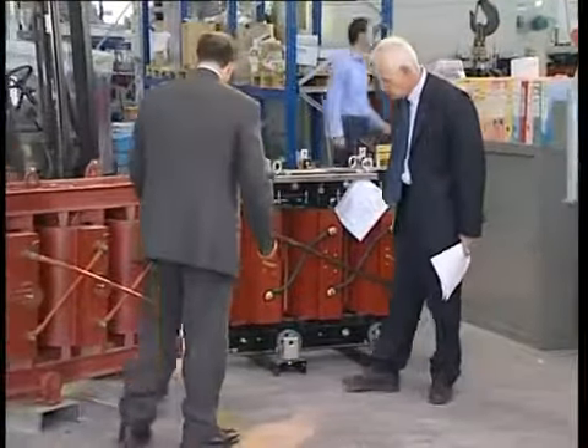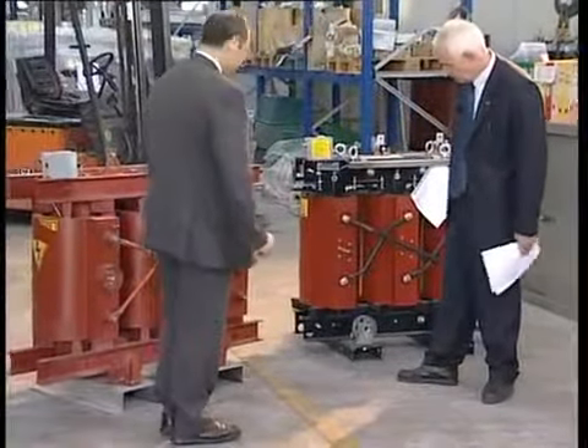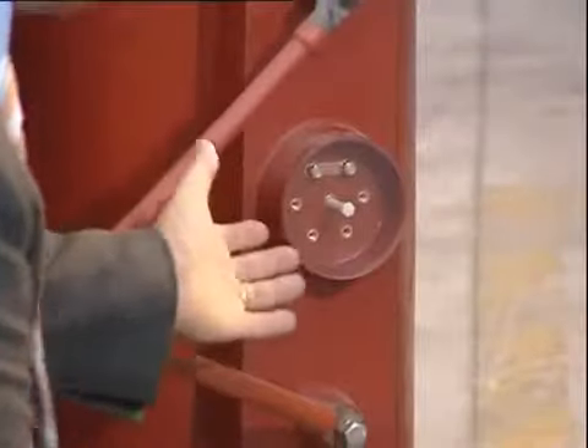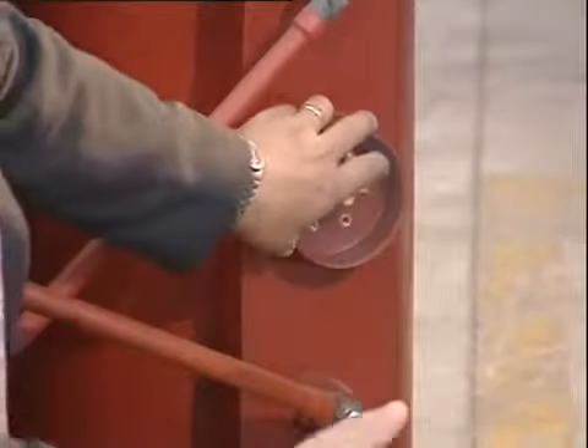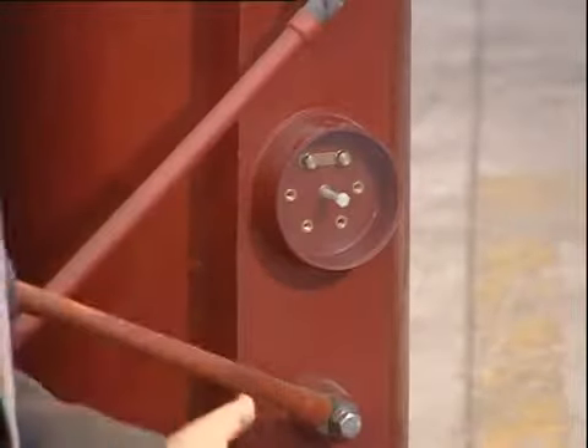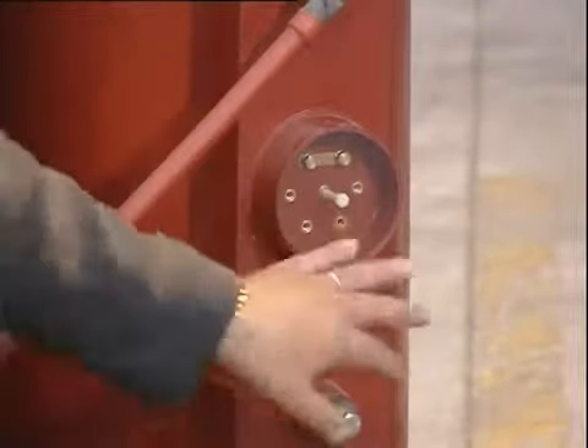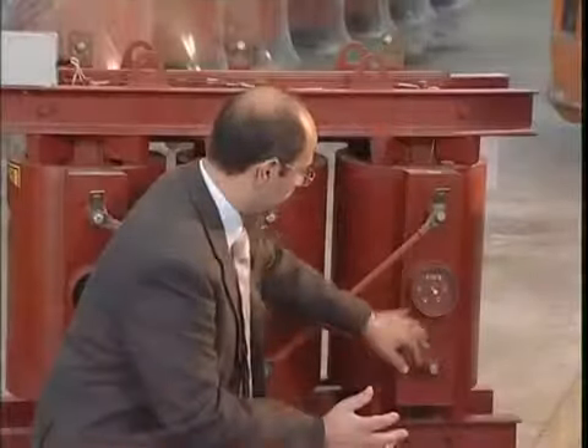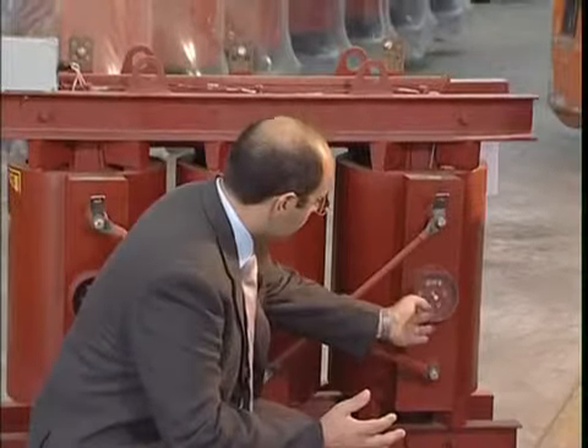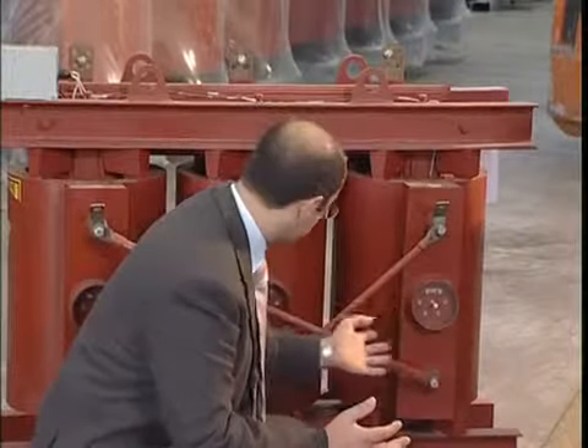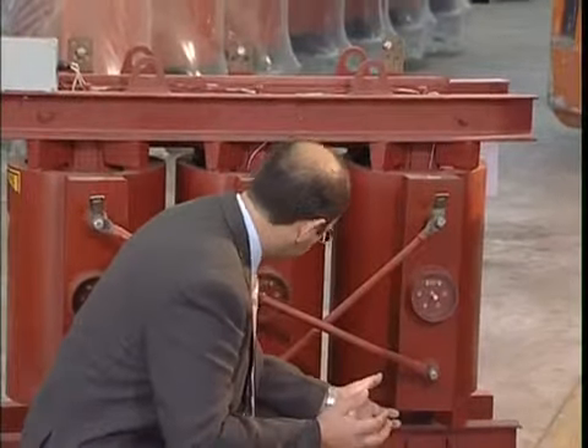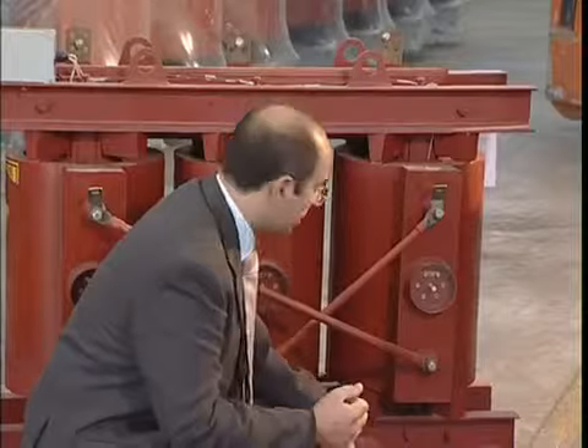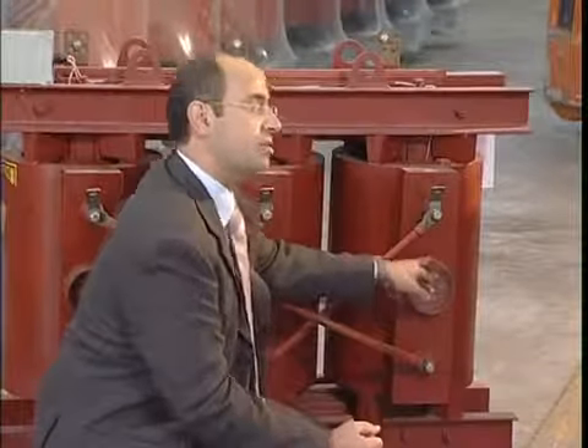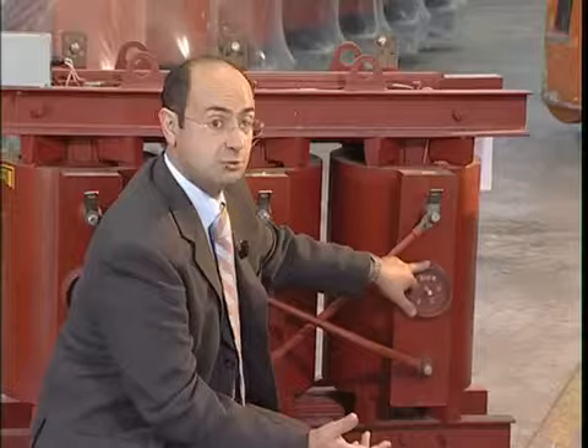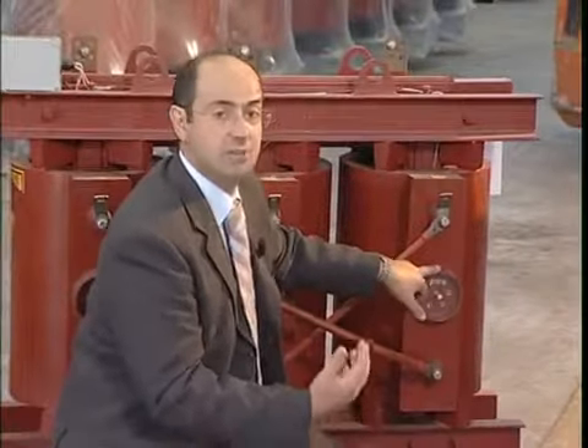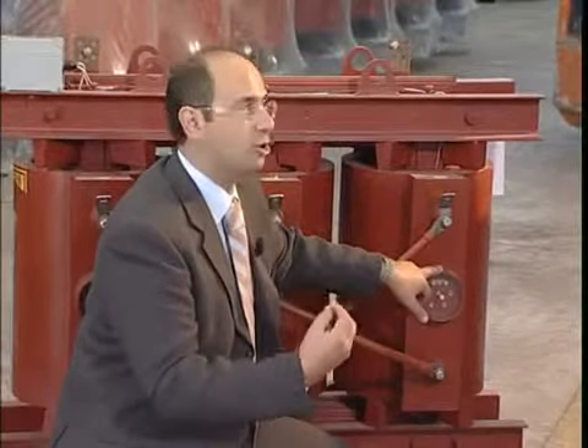Conversely, if we look at our competitor's transformer, we can see that the adjustment ring nut is well protected. And I cannot understand against what. Also because here everything is at hand. Sure, the terminals are apparent, while the adjustment ring nut is protected. I can't see any numbers here. Exactly. There is no indication identifying the various tapping points. Consequently, it is easier to make a mistake. It is far easier to make a mistake. Probably the indications can be found in the instruction manual, which, unfortunately, is often lost a few days after installation.